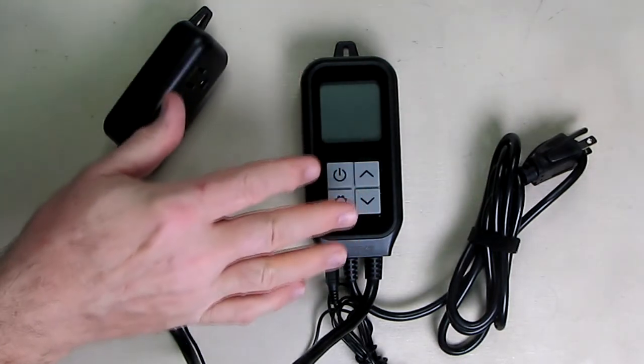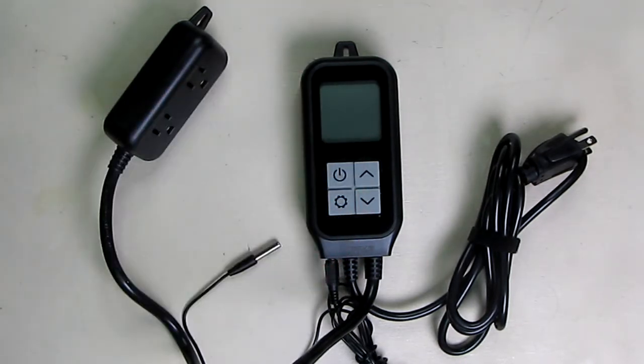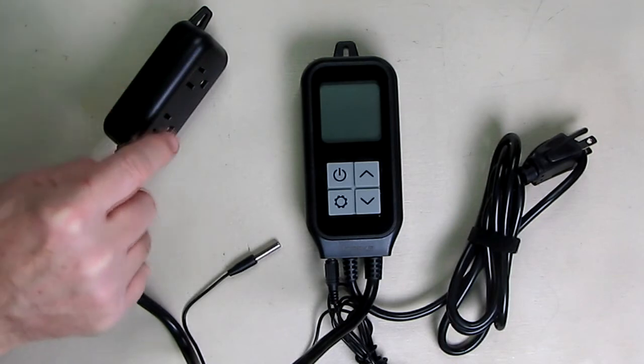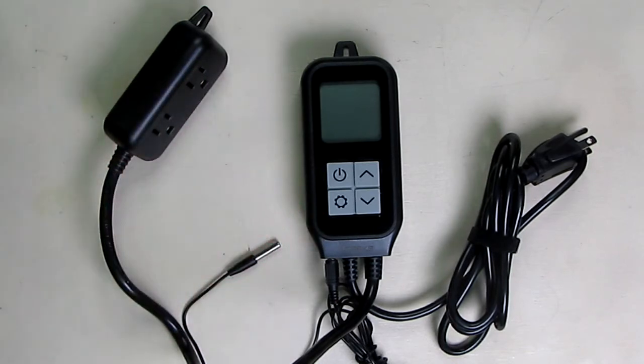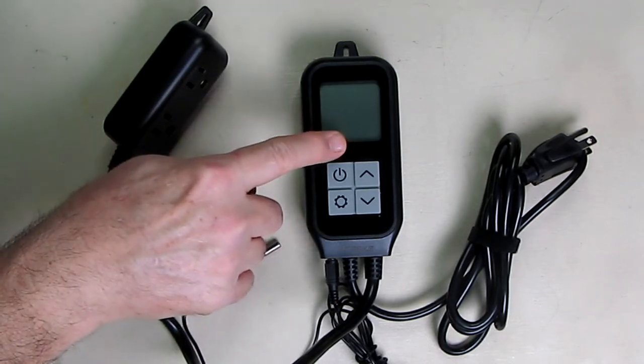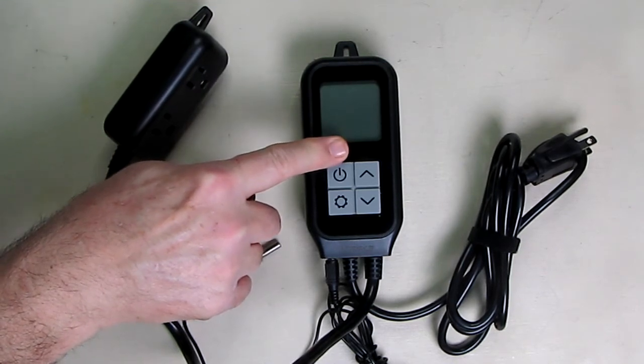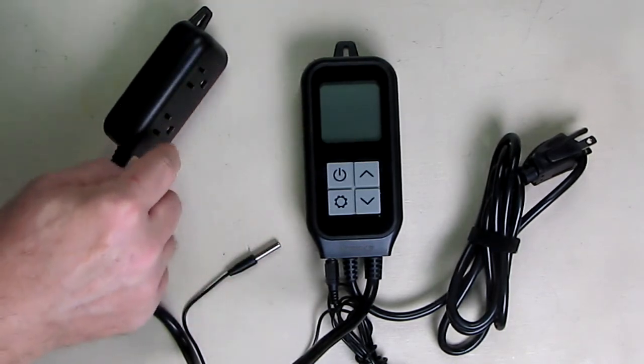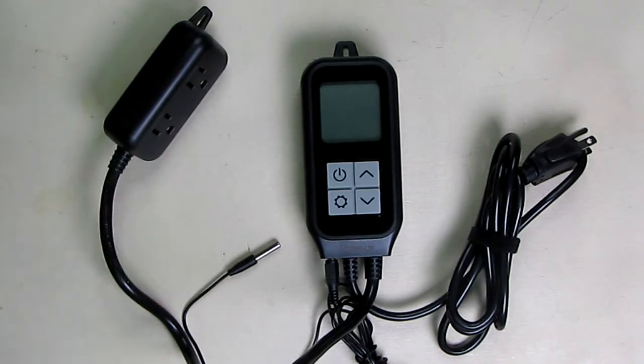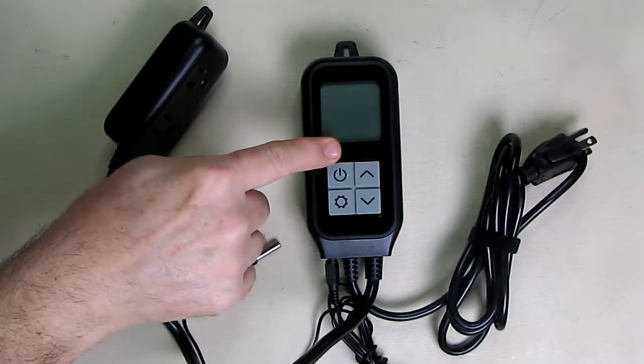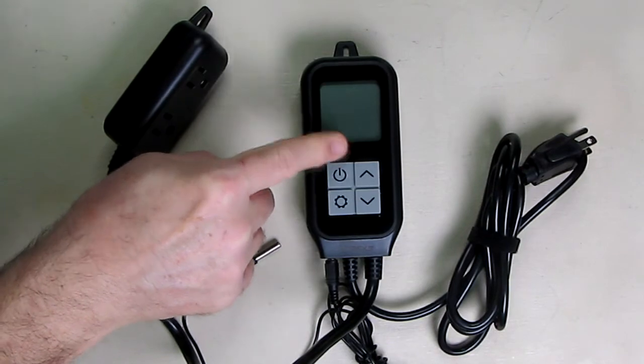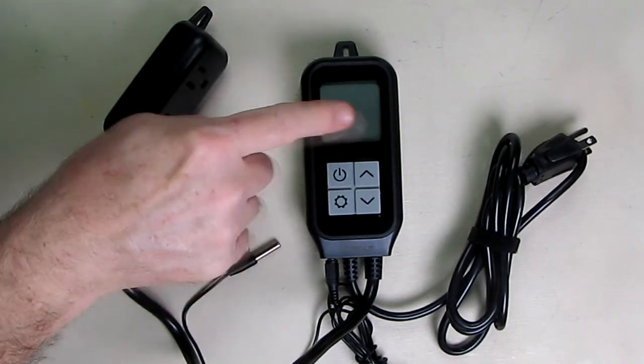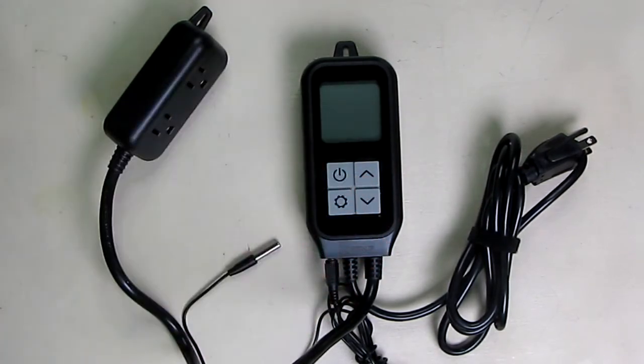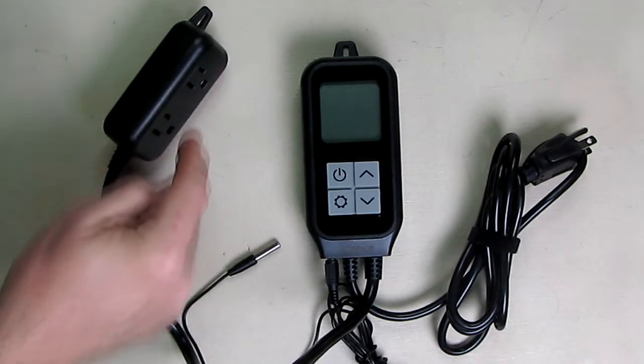The way all these work is they turn on heat or cool when the temperature rises or drops. This unit triggers a relay response with a rise or drop of 5 degrees Fahrenheit. There's a slight delay for safety, 10 to 15 seconds, so when the temperature goes over 5 degrees it delays slightly so you're not hunting with your equipment. That saves on energy and on the components of whatever you're driving with this.